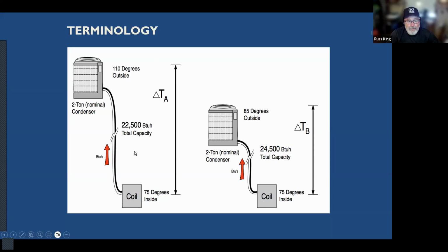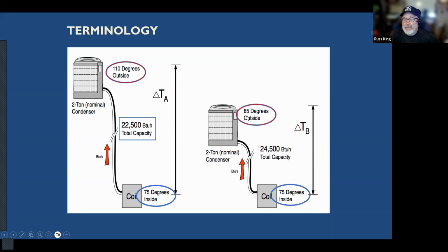So you need to know these conditions when you're actually sizing an air conditioner. And you should know those conditions because you'll need those to do your load calculations as well. So the same conditions that we use for our load calculations, we take those same numbers and use them. And you can go to these big, huge, ugly, gigantic tables that the manufacturer provides, and you can actually look up these numbers based on the outdoor temperature or the difference between the indoor and the outdoor temperature, and a few other things like airflow and stuff like that. Okay. So we've got 110. Oh, I forgot there was animation in here. So 110 outside, 75 inside, we get 22,500. If it's 85 outside and 75 inside, we get a little bit more than 24,000. Okay.